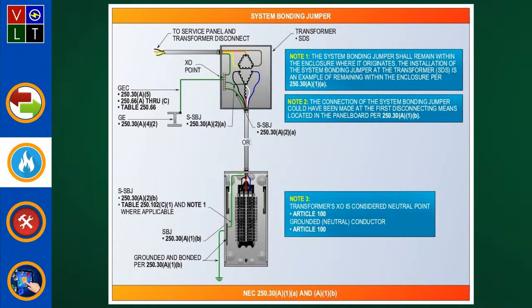So therefore, the system bonding jumper shall be installed and connected at any single point on that separately derived system, and this would be from the source of the first disconnecting means or overcurrent protection device. And if those ungrounded phase conductors are larger than that 1100 or 1750 for aluminum, then the system bonding jumper at that point will normally be larger than what? The grounding electrode conductor. Right.